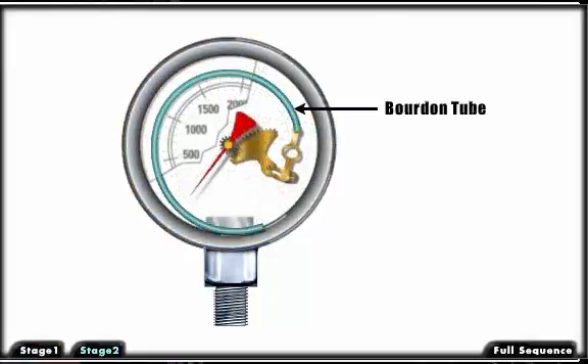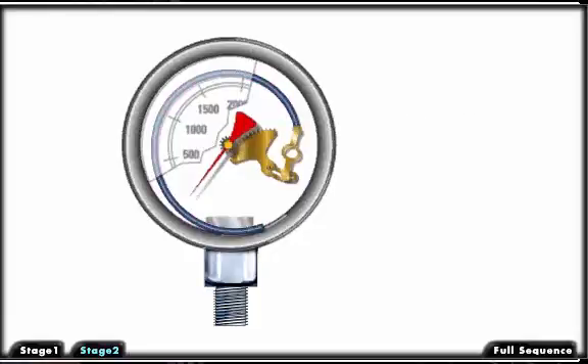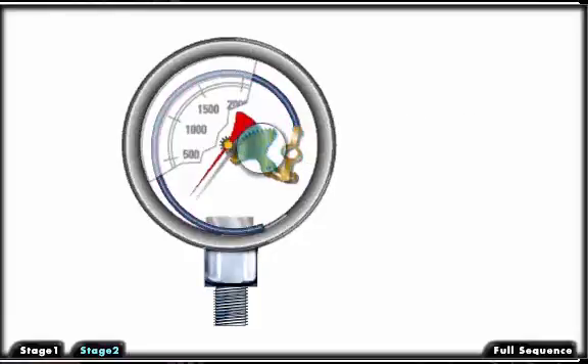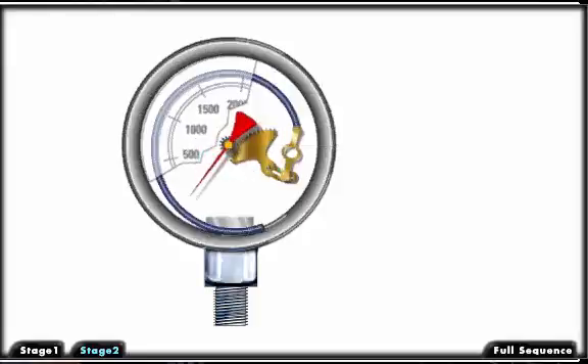The bourdon tube is a coiled metal tube connected to system pressure. Any increase in pressure within the system causes the tube to straighten out. The end of the tube is connected to a mechanical linkage which turns a gear. This gear, in turn, meshes with a gear, driving the pointer needle. Watch now as the tube is pressurized, causing the needle to turn and give the new system pressure.